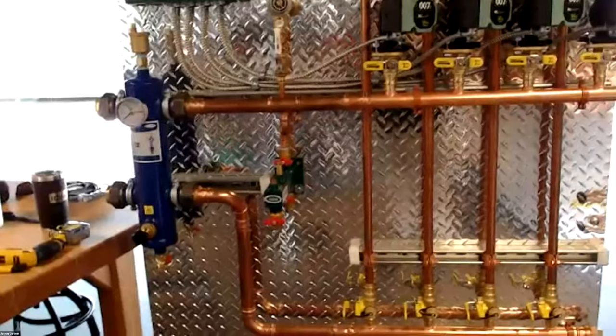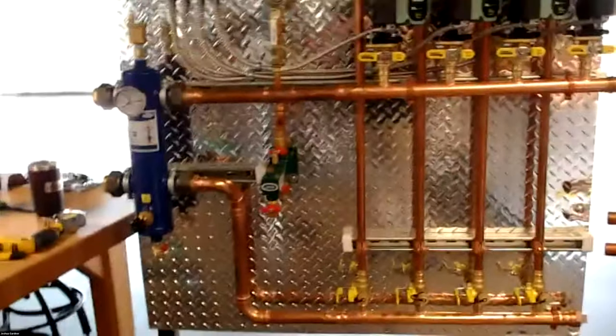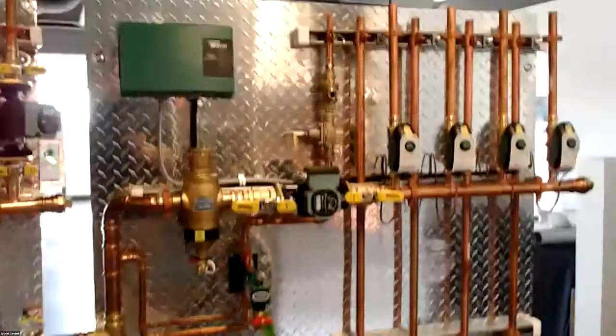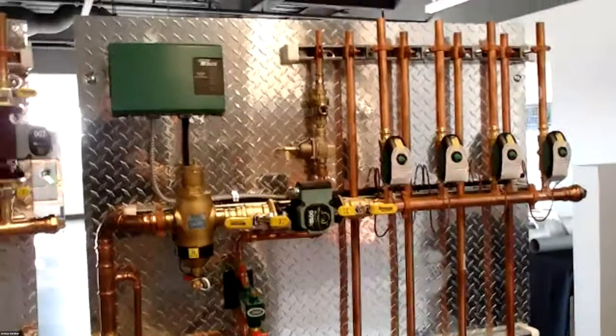Just showing the secondary side. Again, our boiler realistically is just meeting the demand of that low loss header. The secondary side is hydraulically separated on its own. So if you want to use zone valves, you want to use system pumps, totally fine. ECMs, it doesn't matter, but we just need that hydraulic separation between our two systems, okay?